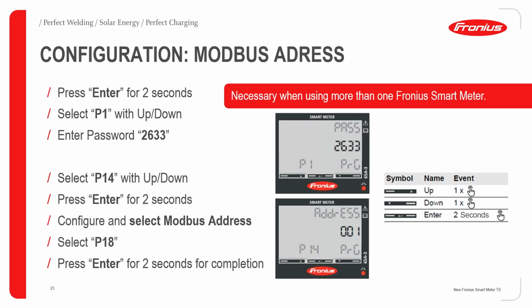So now you have set up everything in the inverter, but how do you set up an address to the smart meter itself? Like as I said, if you are using multiple smart meters, then how do you name it? Well, if you see the rightmost picture, it shows what the symbols at the bottom of the smart meter display mean. So this symbol is up, which shows the up arrow. On the right side is the down arrow, that's the down. Navigating in the menu, you can go down. And then the center symbol is the enter.